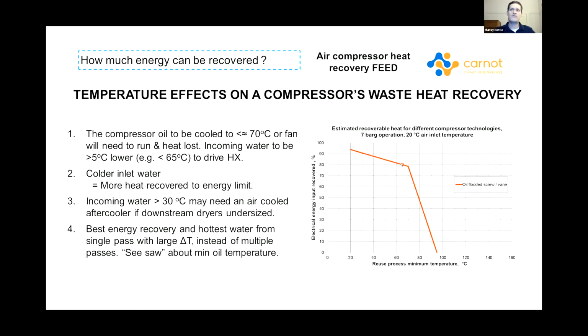Now, if that water is only heated 5 degrees, it's going to go out at 65, and you won't be able to use that water again to recover the rest of that heat. Whereas if you've got a 25 to 30 degree rise in that water, you can heat the water all the way up to the maximum it can do from that 65 degrees coming in. So it's really important to go with a single pass on your water, not lots and lots of little passes, but a single big temperature rise.